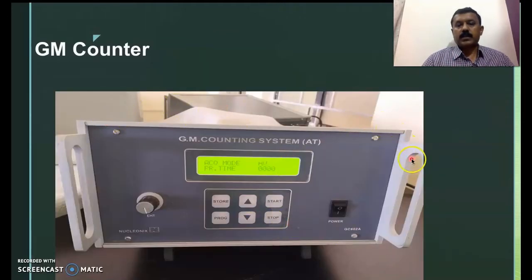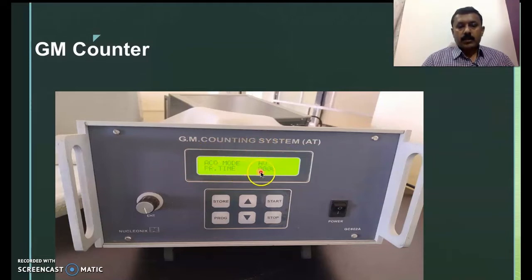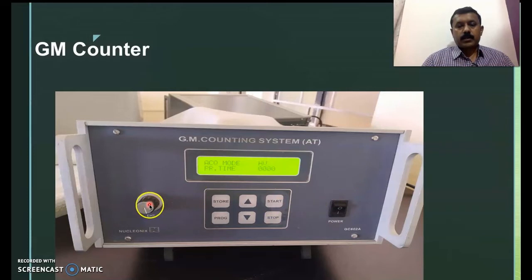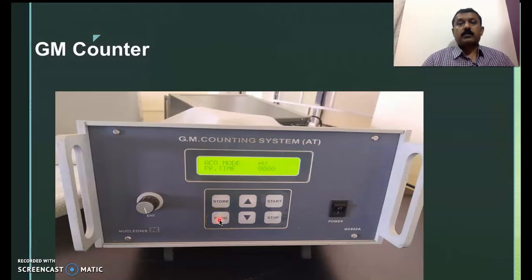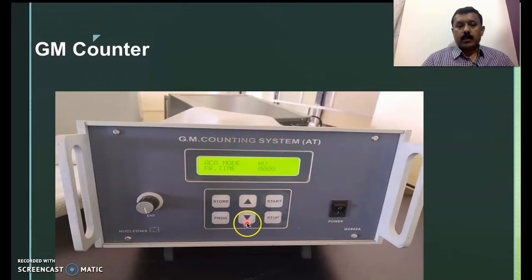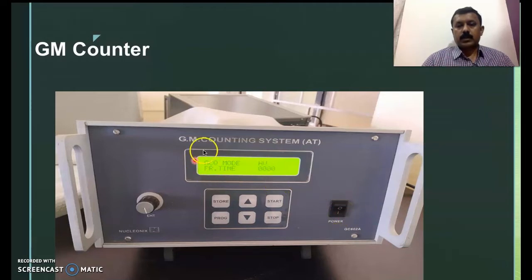This is the panel of the GM counting system — a Nucleonix make. There is a knob to set the operating voltage; before switching on, keep it at the minimum position. There are program buttons to set the preset time, a start button, a stop button, and upper and lower arrows to set time and other parameters. There is also a power button to switch on and off. For different GM counting systems, the panel layout will differ.